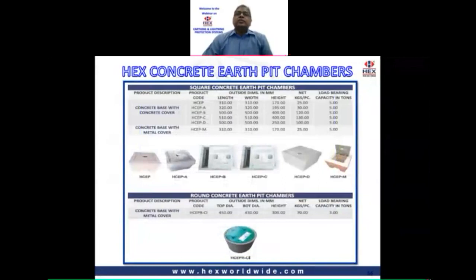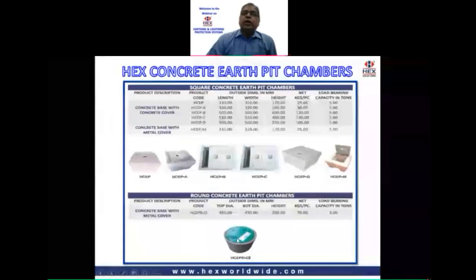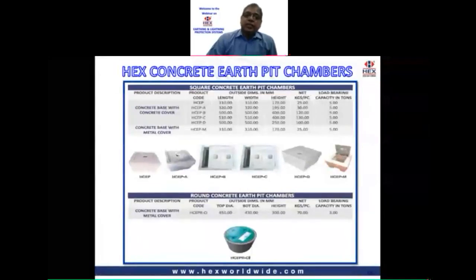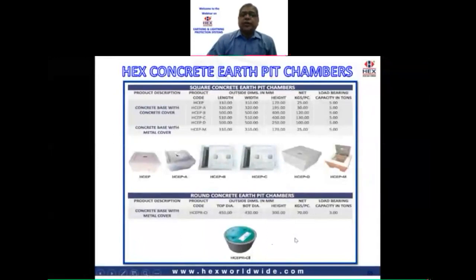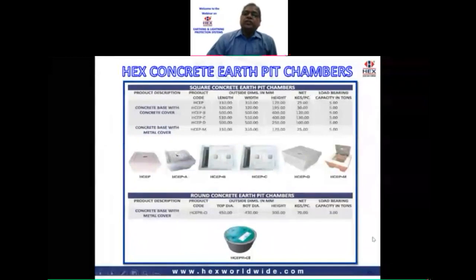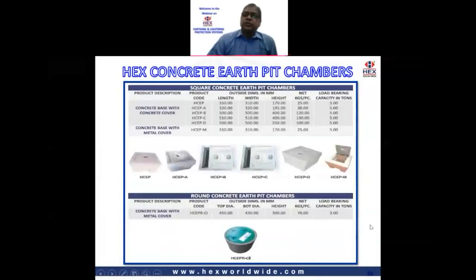The Hex also has ready-to-use concrete and polymer earth pit chambers. Now, these are our chambers made from concrete. We have six sizes in all, of square shape and one in the round shape. All the square chambers have been tested successfully for a load-bearing capacity or LBC of 5 tons, whereas the round chamber has passed a LBC of 3 tons. This was a customer requirement, so it was built accordingly. Even the standard, that is IEC 62561-7, which governs this, states that these chambers have to pass 3 tons.